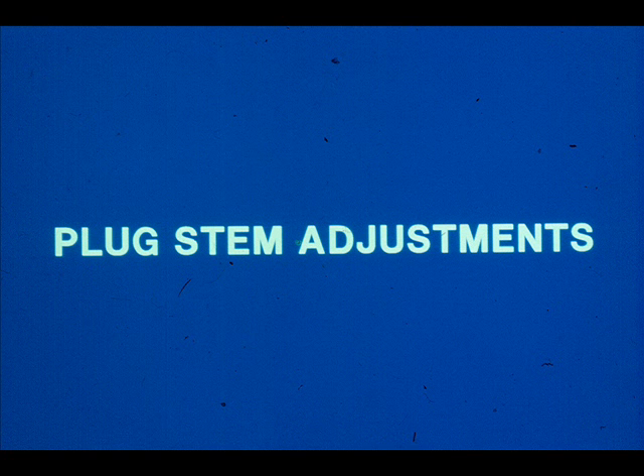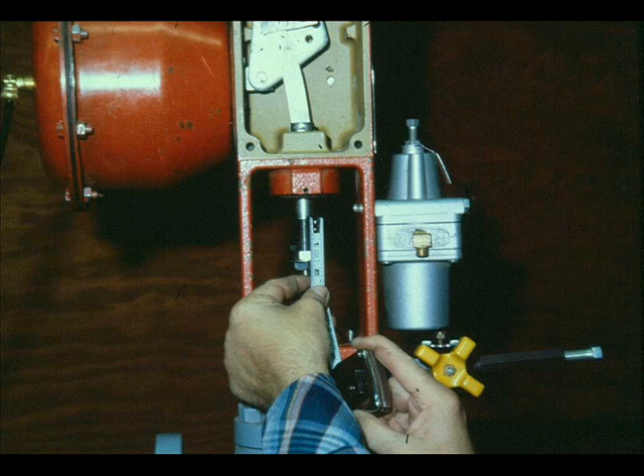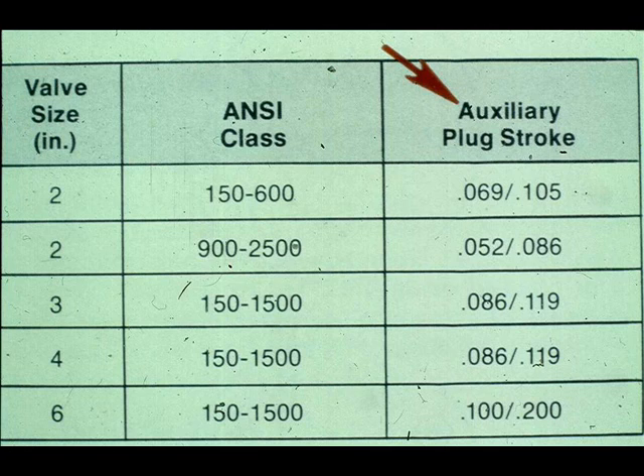Masoneilan recommends the following plug stem adjustment for most of their single and double-seated globe valves and cage valves. For air-to-close valves, separate the plug stem and actuator stem, push the plug stem down until the plug seats. With no air pressure on the actuator diaphragm, position the lock nuts and indicator disc on the plug stem so that the distance from the top face of the top lock nut to the bottom of the actuator stem is equal to the required valve stroke. For the 41400 series valve, an auxiliary plug stroke must be subtracted from this distance.